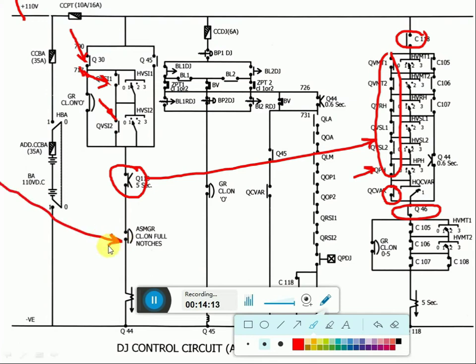Manual operation of GR should not be done if Q44 is wedged. If Q44 is wedged, with manual operation, if you take excess time also, DJ will not trip, RGR may burn. So if we wedge Q44, we should not do manual operation. These precautions we have to follow for Q44 wedging.